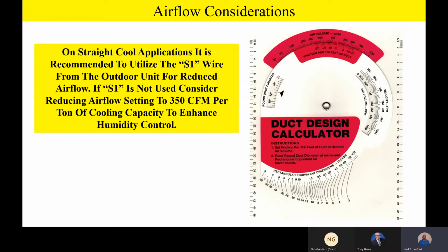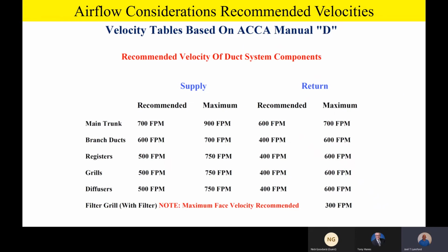And so once you commission it and you set your airflow up and you've got your ductwork properly sized, if you need to back off your airflow a little bit to 350, you're perfectly fine to do that if you need some extra humidity control. And then finally, we want to make sure that everyone considers Manual D as our airflow and duct design criteria. Let's make sure that we don't exceed the recommended duct velocity in our main trunks and our branch runs, because it's important that we have the air going across those heat exchangers on the indoor coil at the proper velocity as well.